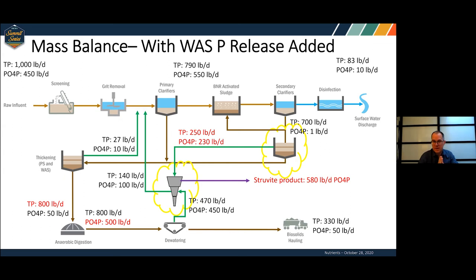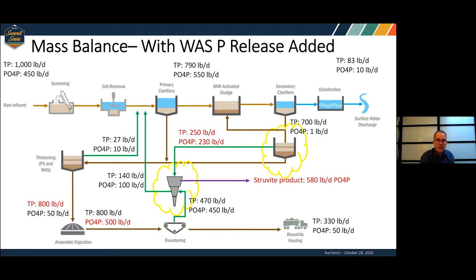With something like a WASSTRIP process, you take your WAS and send it to a phosphorus release tank. Now you've got two different streams going to your struvite recovery process: one from the WAS and one from the filtrate. This increases the amount of struvite you're pulling out — the highest amount we've seen in these examples. Because you're pulling more out, you get benefits all over the plant: lower secondary influent levels, lower digester levels, and lower levels hitting your dewatering process.